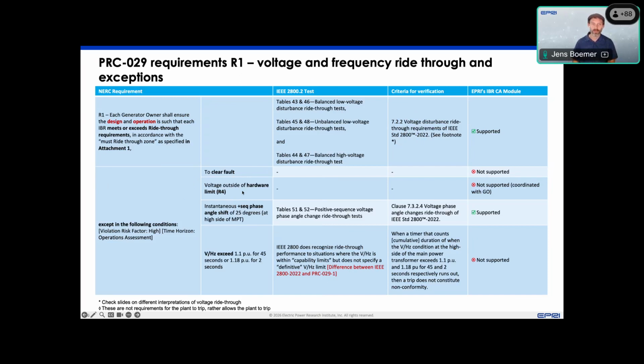Also, any hardware voltage being outside of the hardware limits, if there is a hardware limit that is smaller than the ride-through curves and the protection systems are not adequately represented in the models, then that would not be caught by our tool. That might require some review of documentation, but anything included in the model itself can be assessed by the tool and would then show some tripping and non-conformity.